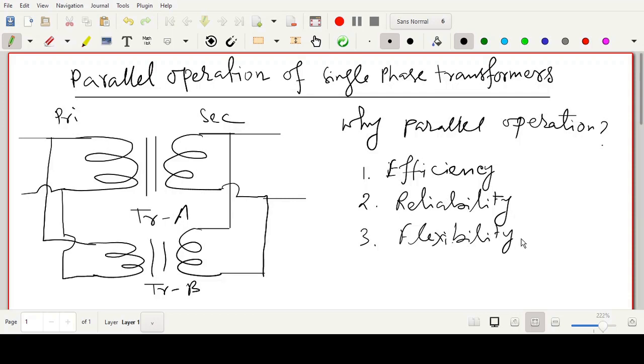What is flexibility? Flexibility means if you want to take up maintenance work for the transformers, you can give power from those which are in operation. You can shut down the transformer which requires maintenance. In case of a single transformer, your load has to be put off. This flexibility is there in case of small transformers operating in parallel.